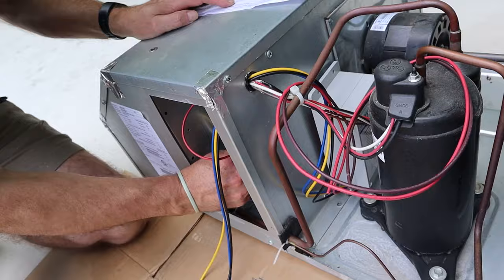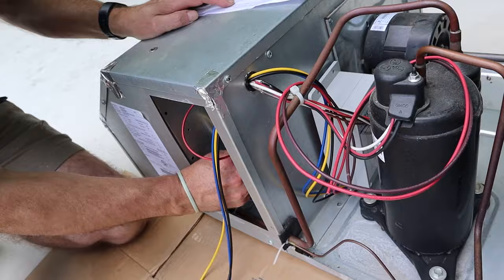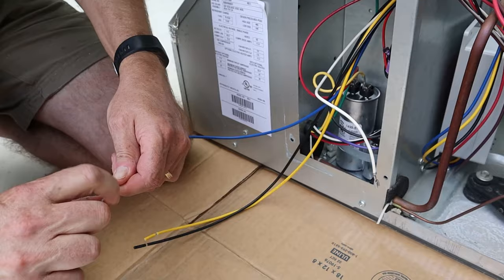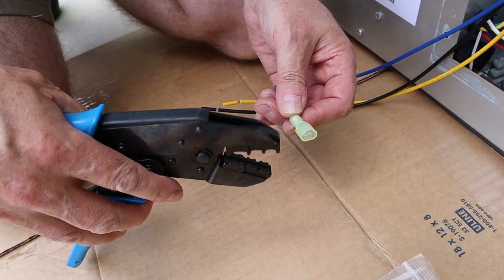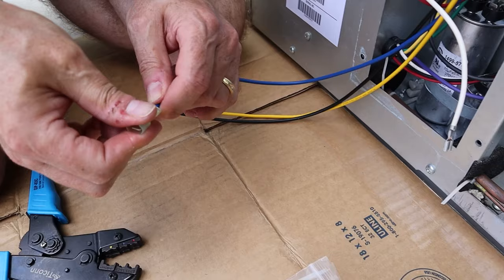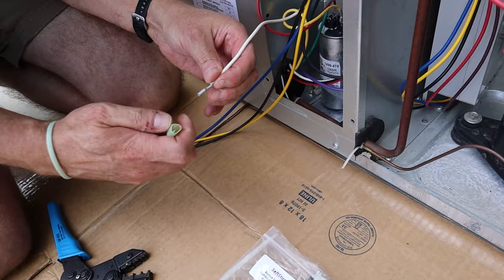Follow the white compressor wire to the run capacitor and disconnect it from the terminal. Connect it to the blue soft start wire. We're going to tape them — the instructions say to tape them, so we're going to tape it.